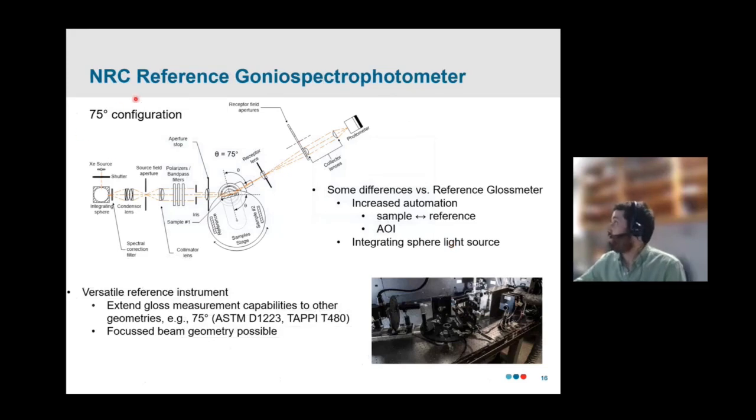So at this point, I'll move on to describing our reference goniospectrophotometer. So this is another instrument that we have at NRC. It's more recent. It was constructed in 2005 and it can measure specular gloss in the geometries, the same geometries as the reference gloss meter. But it can also satisfy the geometries prescribed in other standards. So it can do, for example, 75 degrees angle of incidence. And it's also capable of realizing a focused beam geometry, which is called for in certain standards. I think this TAPPI standard, for example, requires that.